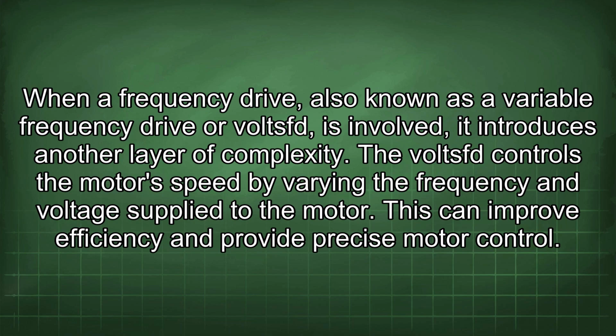When a frequency drive, also known as a variable frequency drive or VFD, is involved, it introduces another layer of complexity. The VFD controls the motor's speed by varying the frequency and voltage supplied to the motor. This can improve efficiency and provide precise motor control.